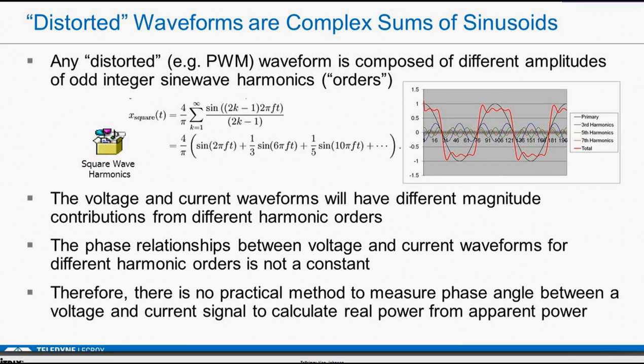What makes it difficult to make measurements is that every voltage and current frequency will have different magnitude combinations from different harmonic orders, and the phase relationships between the different harmonic orders will be different. So they're not all the same. It's not a constant. Therefore, there is no practical method to measure phase angle between a voltage and current signal when you're dealing with a very distorted waveform. So there's no practical method to simply calculate real power from apparent power. You just can't do it. So a different approach is needed.